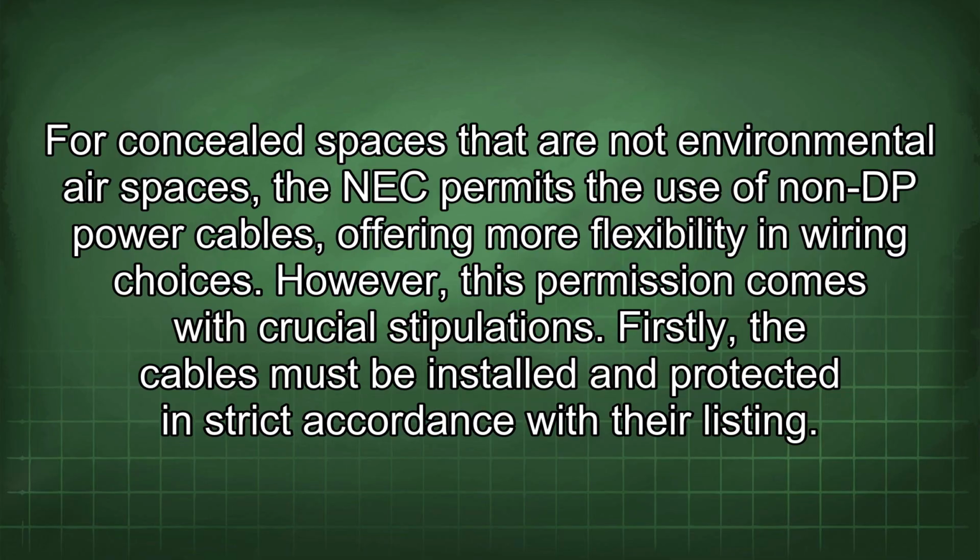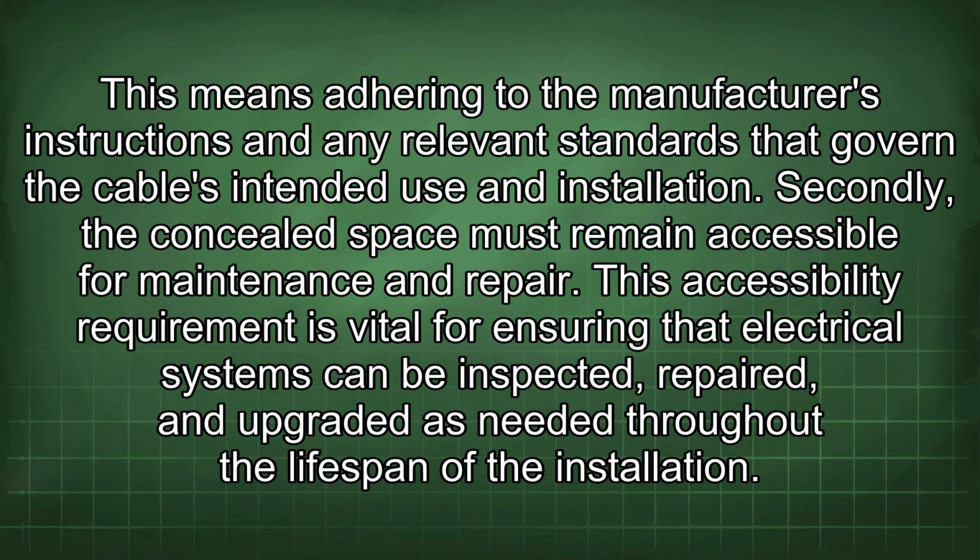Firstly, the cables must be installed and protected in strict accordance with their listing. This means adhering to the manufacturer's instructions and any relevant standards that govern the cable's intended use and installation. Secondly, the concealed space must remain accessible for maintenance and repair.